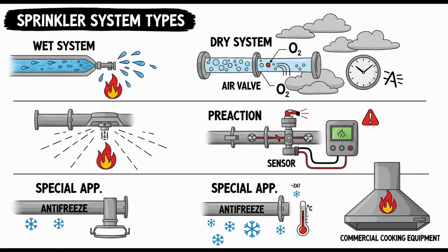What if it gets even hotter? If temperature monitoring or assessment indicates that ambient temperatures during operation regularly exceed 300 degrees F, then an even higher temperature classification sprinkler or nozzle, like very extra high or ultra high, is required. For K factors, which relates to orifice size and flow, the standard requires a minimum K 1.4 and a maximum K 5.6 for sprinklers or nozzles used in these specific duct, collar, and plenum locations. So very high temp ratings are standard, and K factors are generally on the smaller side, likely designed for the specific flow needed to coat surfaces or fill these confined spaces effectively. Yes, tailored for the hazard.